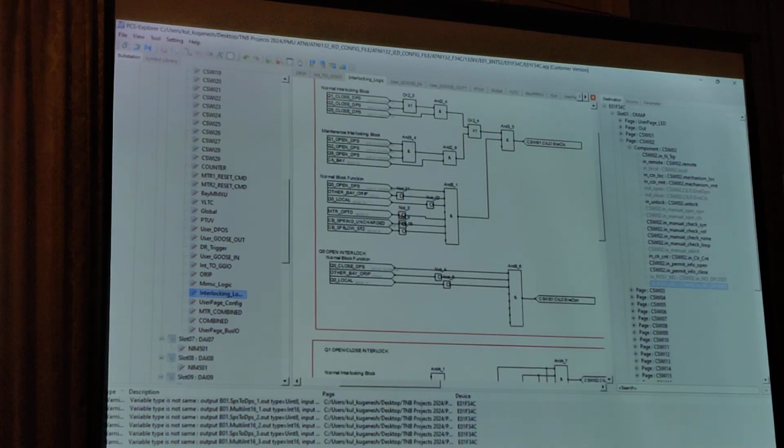So let's say all are satisfied, then only the close interlock will be given. I mean the interlock will be passed. But let's say suddenly CBSF6 low stage 2 high, then the NOT gate will get 1, which will invert it to 0. So this AND gate won't be satisfied, and that will cause an interlock.